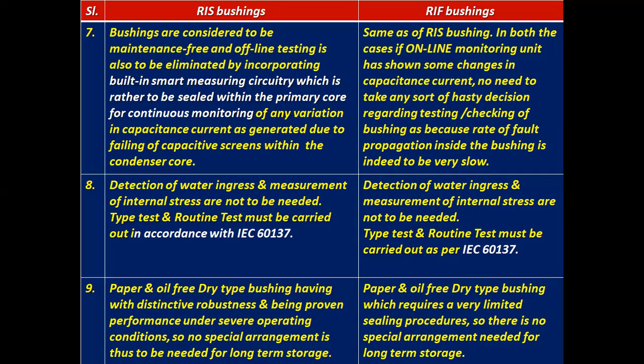Number 9, the paper and oil-free dry type bushing has distinctive robustness and proven performance under severe operating conditions, so no special arrangement is needed for long-term storage. The paper and oil-free dry type bushing requires very limited sealing procedures, so there is no special arrangement needed for long-term storage.